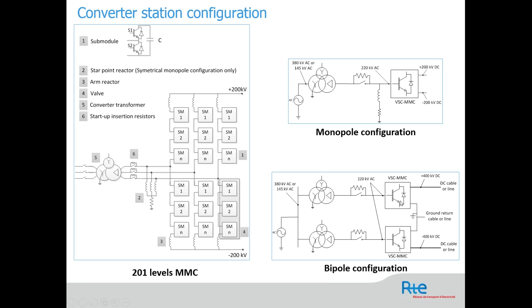Okay, so as I mentioned, you have monopole and bipole configurations. This is the difference between both. The monopole configuration uses one MMC converter with a star point reactor to have a reference to ground, because you don't have any reference to ground on the DC side. And then in the bipole configuration, you have 2 MMCs and 2 transformers, and the grounding is on the DC side in this case. So you don't need the star point reactor.